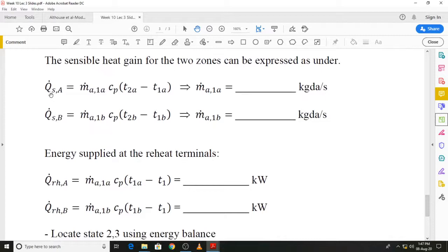Okay. So the sensible load for zone A is given to us. Mass flow rate for zone A is to be worked out. Specific heat for air we will take as the standard value of 1 kilojoule per kilogram Kelvin. The temperature T2A we were given, T1A we have found out, so you will find out the mass flow rate for zone A, and along the same lines you will find out the mass flow rate for zone B, and that is in kilogram dry air per second. And once we know the mass flow rate to each of the zones, then we can find out the energy supplied at the reheat terminals.